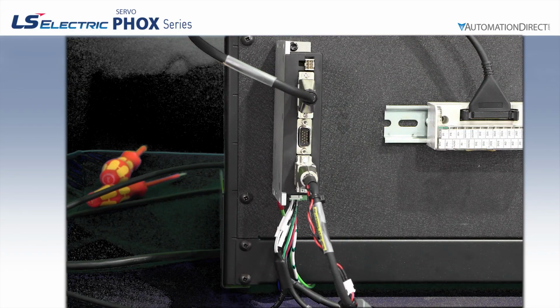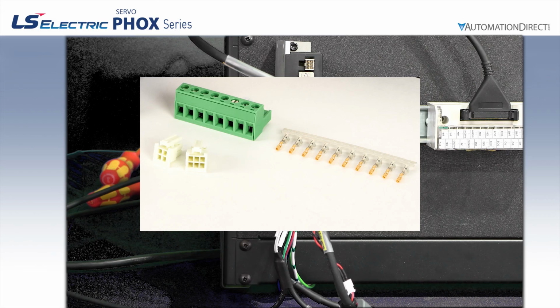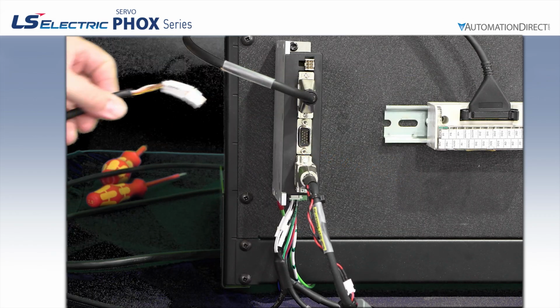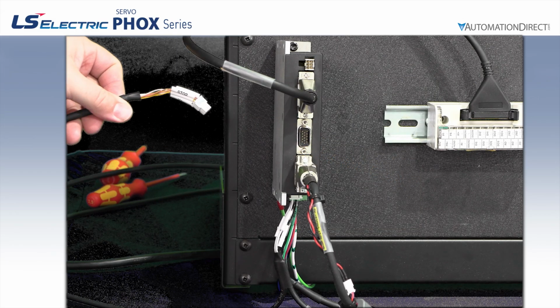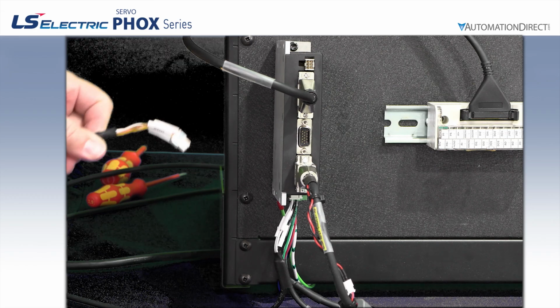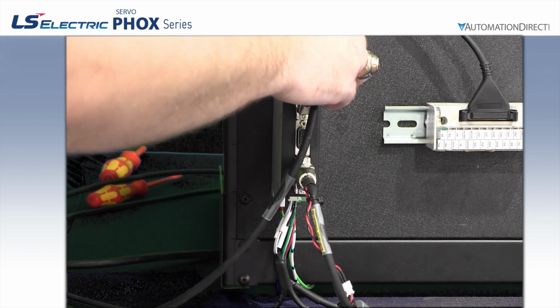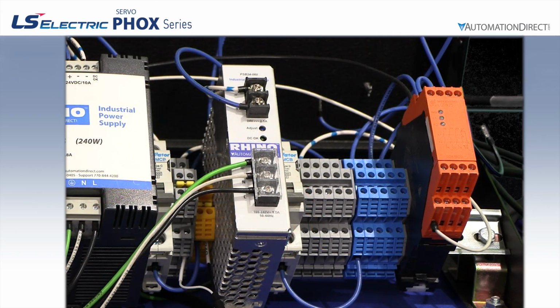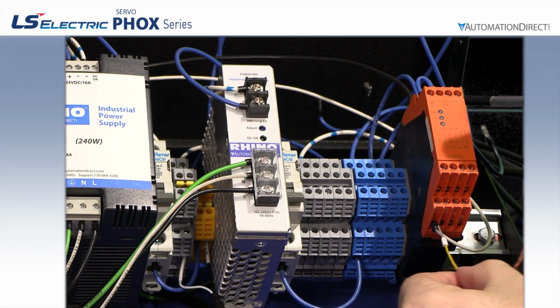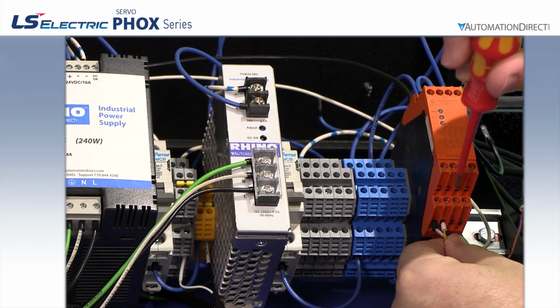We are also using the STO function with our emergency stop. You can use the crimp pins and blank STO connector that ship with the drive, but for only a few bucks more, it's much easier to use the pre-terminated STO cable. They come in various lengths, and we strongly recommend that any motion system use a safety relay in conjunction with these STO terminals. Plug the terminated end of the STO cable into the drive's STO connector. Then land the STO 1 and 2 wires on the normally open dry contact outputs of the safety relay.